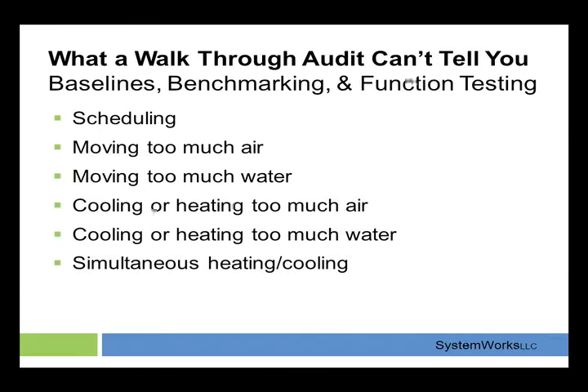Simultaneous heating and cooling. I don't know how many times we'll go out to a job and we'll find the unit heating in the cooling mode, and the heating valve is leaking heat past it. So you're heating and cooling simultaneously, so that you're running the chiller and the boiler's on and the heating valve isn't closing completely, so you're putting hot water or steam into the coil, and then you're trying to cool it down with the chiller. Again, it's real obvious, but you can't tell it from a walkthrough.